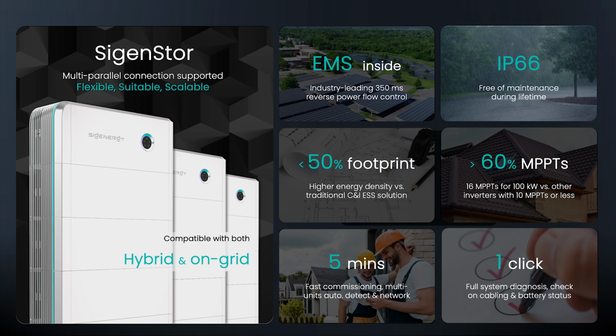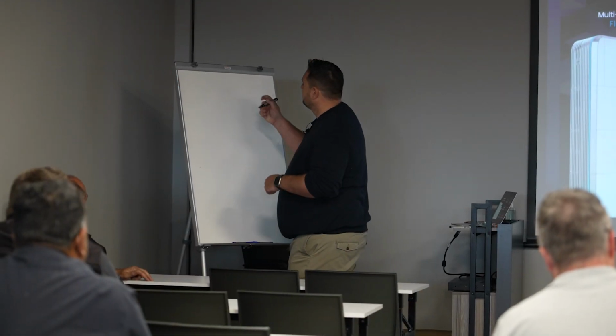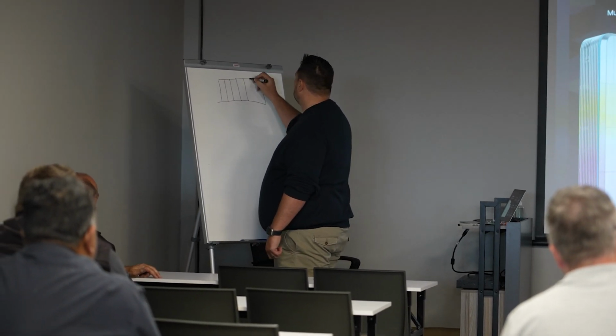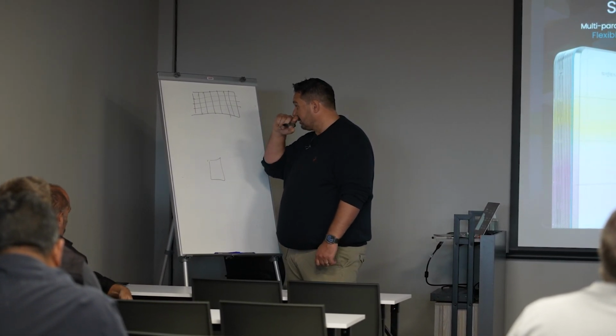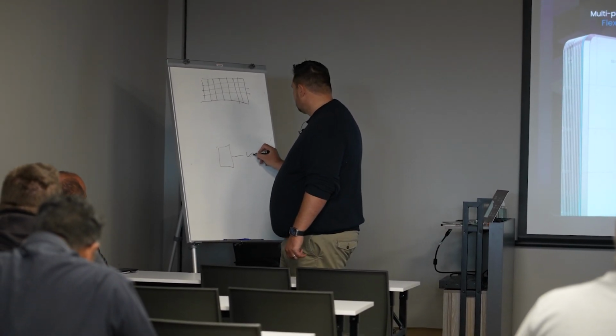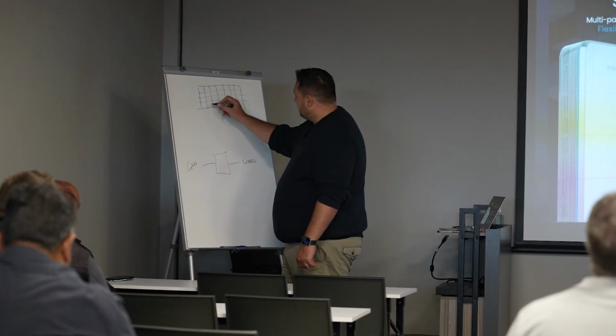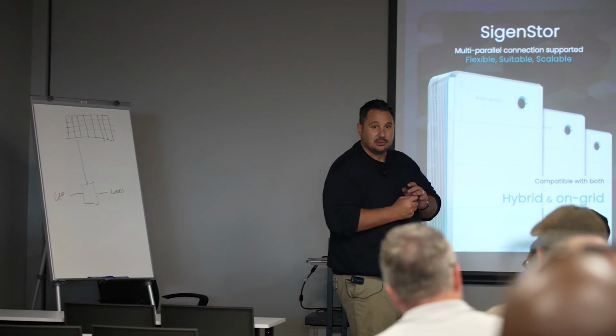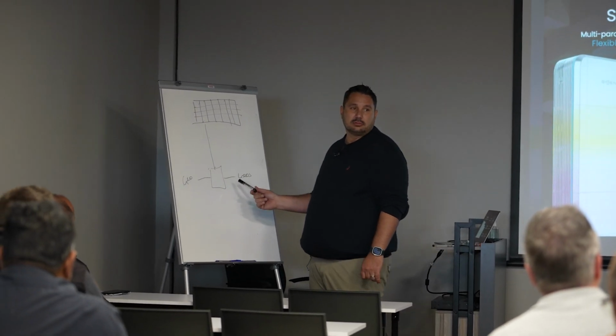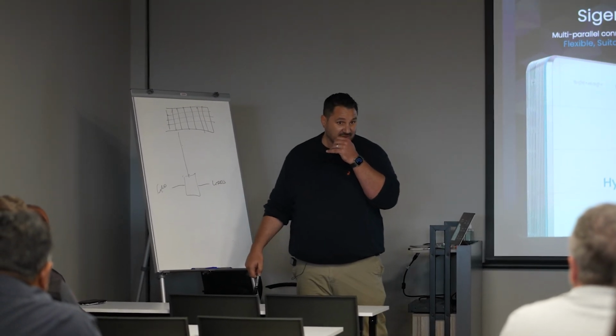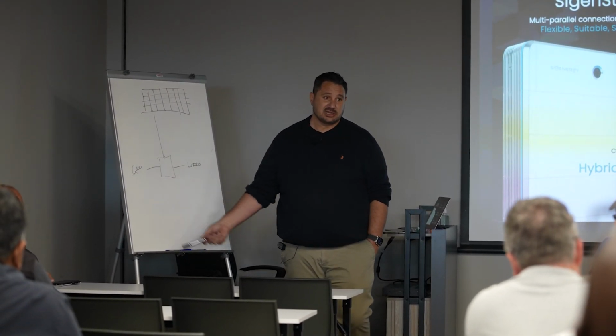I think this is actually something I should touch on. So if we have an installation, let's take this building for argument's sake. So actually a nice installation that we've got here. So you've got your PV on the roof. Okay. So then we've got our inverters inside the building, and we have our loads and our grid input, and we've got our DC cable running there. Where do you think the most losses happen? Here, on the 4-core 70mm cable, or on the 6mm DC cable coming from the roof? That's where the most losses happen.